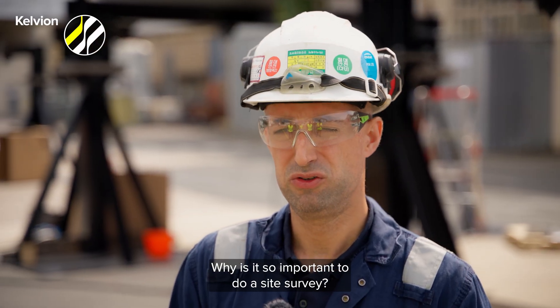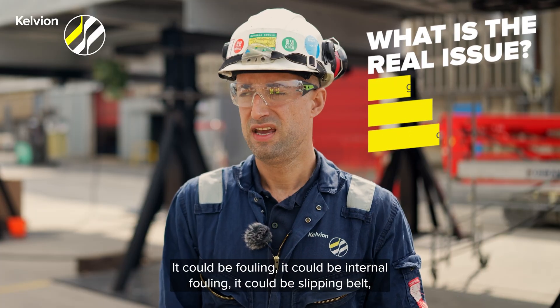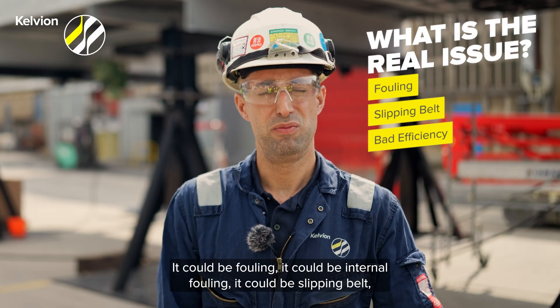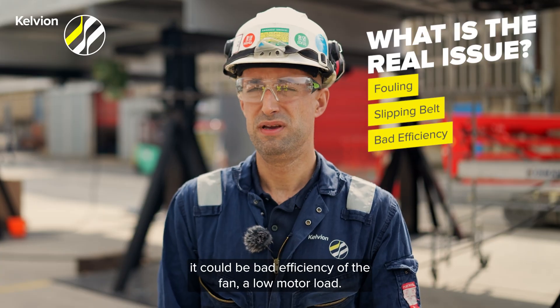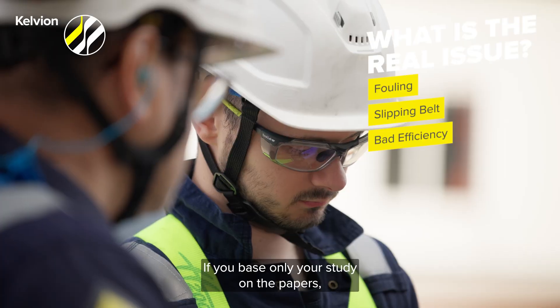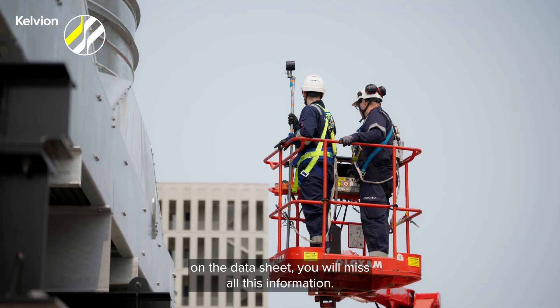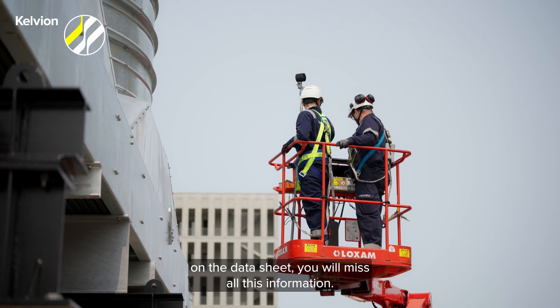Why is it so important to do a site survey? There are many different issues. It could be fouling, it could be internal fouling, it could be a slipping belt, it could be bad efficiency of the fan, a low motor load — there are many, many explanations. If you base only your study on the papers, on the data sheet, you will miss all this information.